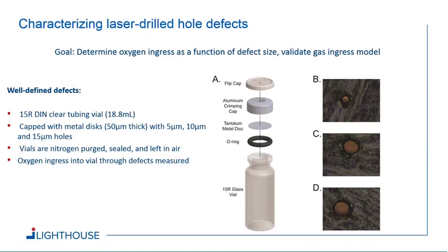And what we use these for as positive controls, we can then very confidently say in our study we were able to detect an ideal hole of 5 microns in diameter, and that's the utility of these types of positive controls. So they have very consistent, well-defined physical dimensions.